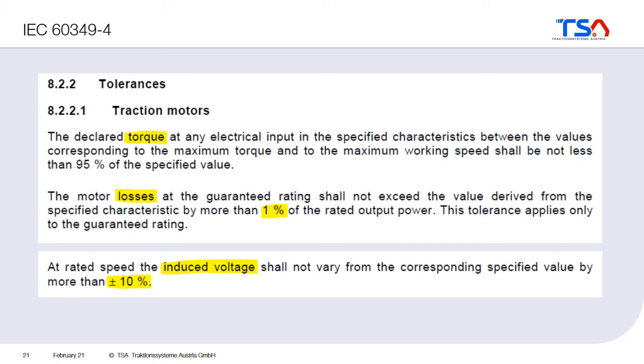The standard also tells us which tolerances are allowed. For torque, it should not be less than 95% of the specified value. For motor losses, they should not exceed the specified losses by more than 1% of the rated output power. The induced voltage shall not vary more than plus or minus 10% from the specified value. This is not always easy to achieve because of tolerances within the magnets — magnetic flux can differ from one magnet to another — as well as variations in magnet size and steel sheet size.